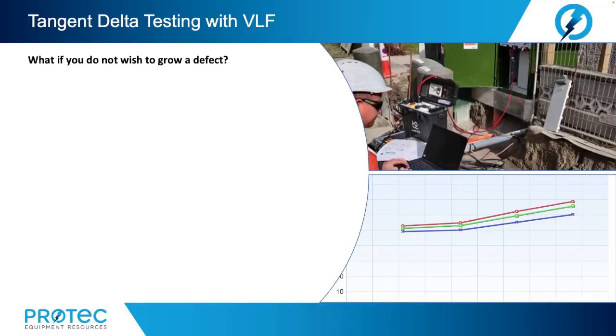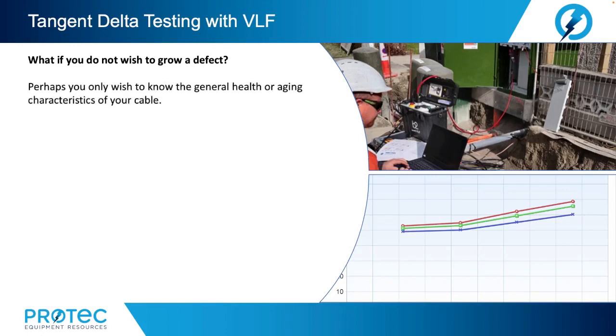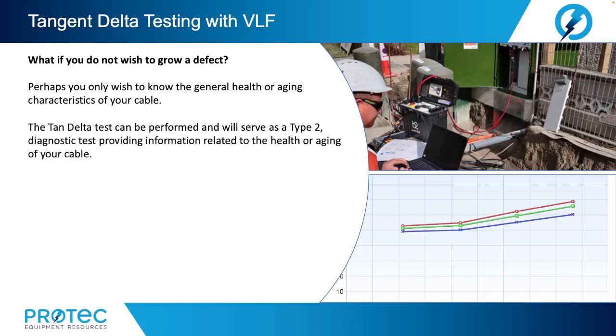So, what if we don't wish to grow a defect? Well, perhaps you only wish to know the general health or aging characteristics of your cable. The tan delta test can be performed and will serve as a type 2 diagnostic test, providing information related to the health or aging of your cable or cable system.